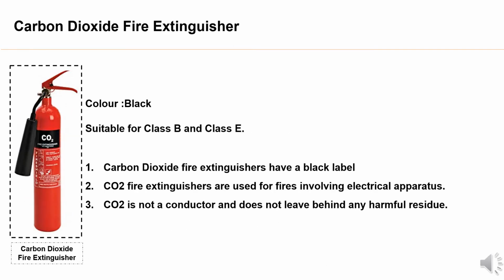Carbon dioxide fire extinguisher. Carbon dioxide fire extinguishers have a black label. Suitable for Class B and Class E. CO2 fire extinguishers are used for fires involving electrical apparatus. CO2 is not a conductor and does not leave behind any harmful residue.